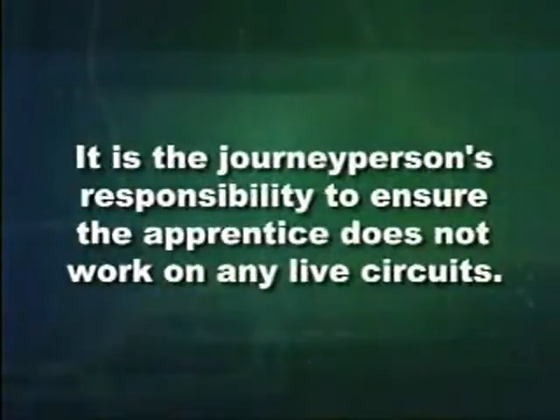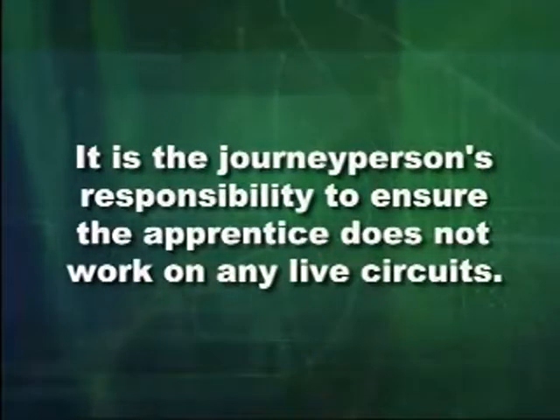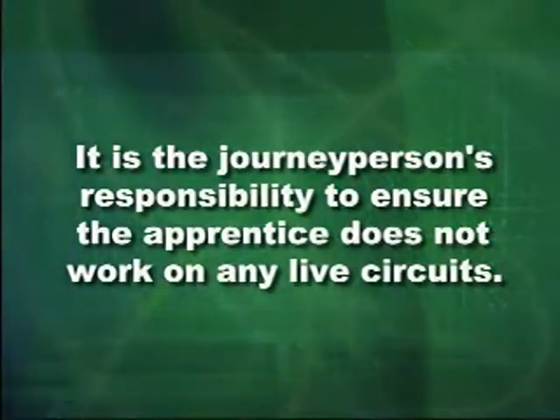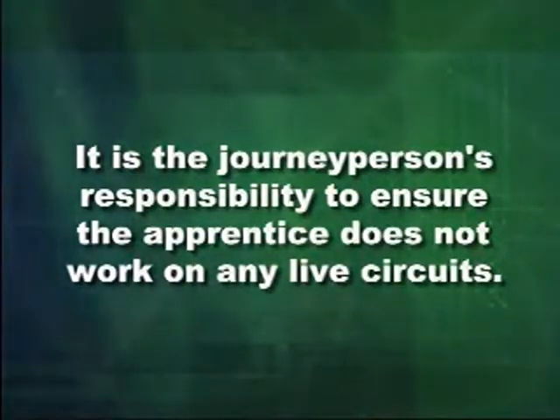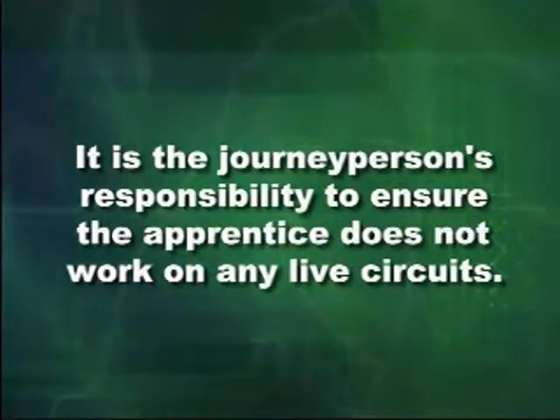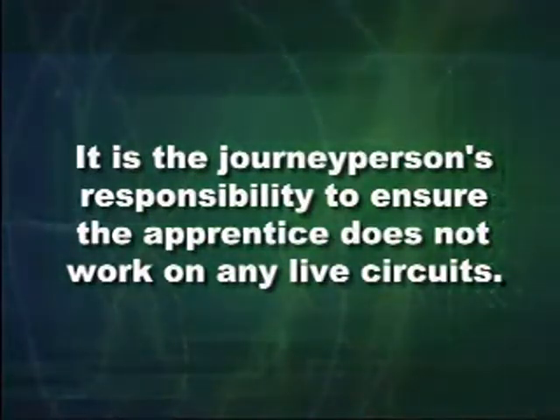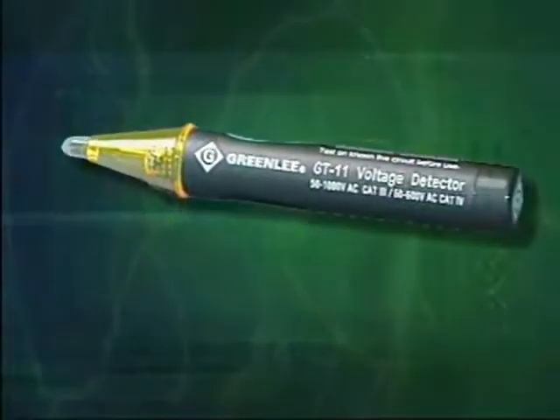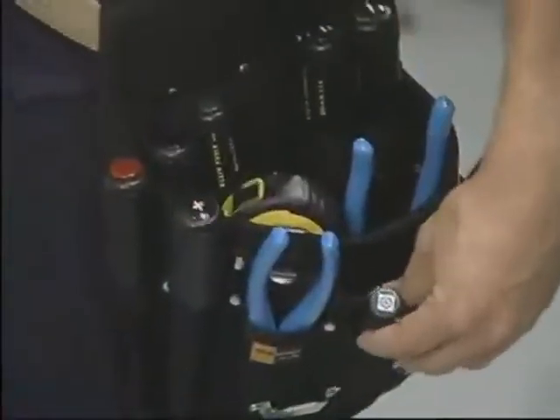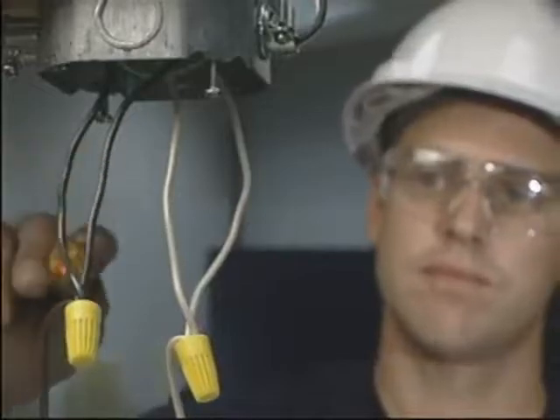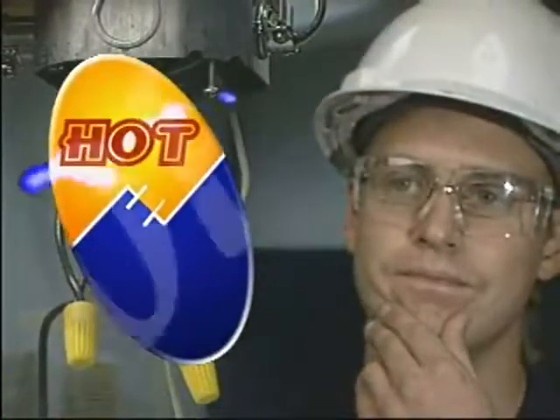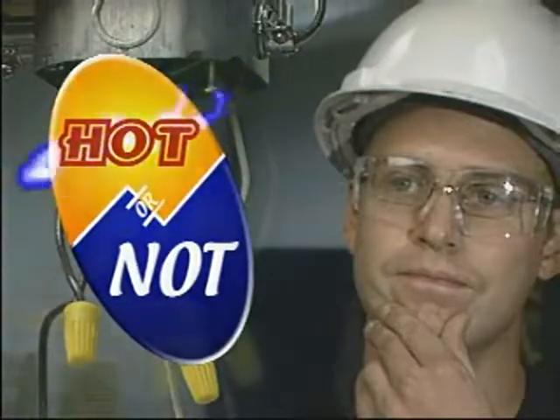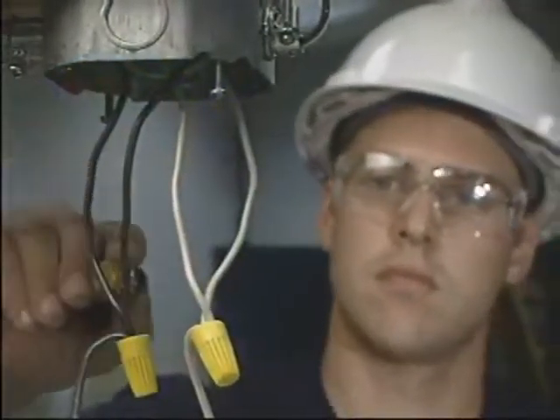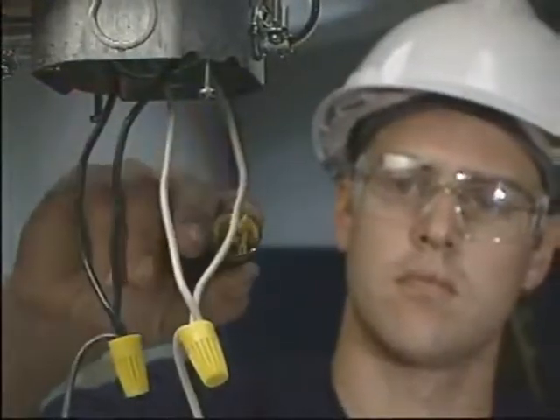It is the journeyperson's responsibility to ensure the apprentice does not work on any live circuits. You should refer to lockout, tagout requirements and company health and safety procedures before proceeding. However, the GT11 now allows you, the apprentice, to confirm you are working in a safe, non-energized condition. Always ask yourself, is it hot or not? If it is hot, see your journeyperson. If it is not, you're good to go.